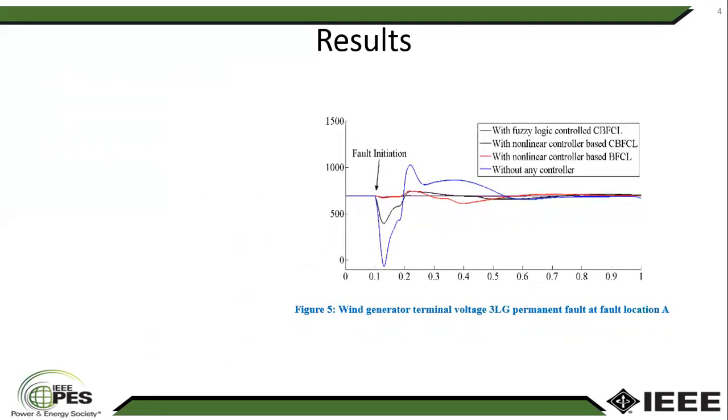For the wind generator, we also checked different dynamic responses. From one of the responses, the terminal voltage of the wind generator, if any three phase to ground fault happens in a specific location of the system, with the presence of our fuzzy logic control CBFCL the wind generator voltage remains stable, whereas the voltage gets a lot of dip in the situation of other operations.